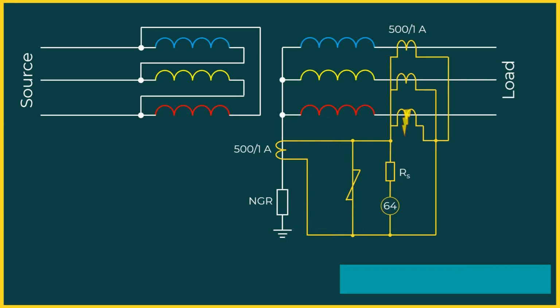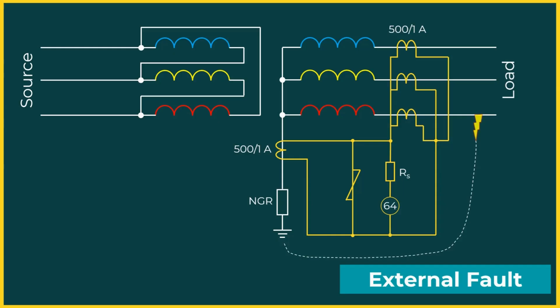it will trip the breaker. Consider an external fault which is outside the protection zone. Under this condition, we can see that there is current through the phase CT and there is also current through the neutral CT, and these two currents are the same. Therefore, there will be no imbalance current which can flow through the REF relay, and hence the REF relay will be stable for an external fault. So we have seen that the REF relay can reliably detect the earth fault current on the LV winding. It is stable for any external fault and it will operate only for an internal fault.